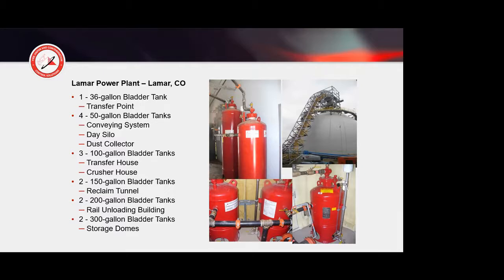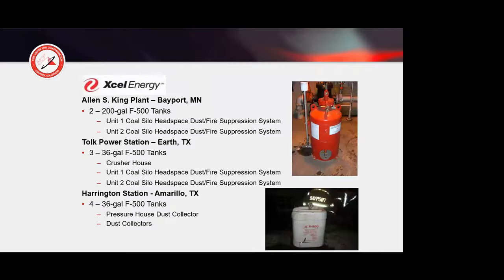Again, there's nothing in the code calling for this, and why they're being installed is because the plain water systems won't work and are actually a detractor and can cause an explosion. So they're putting this agent in to stop that. So usually our recommendation would be 15 minutes with 15 minutes of reserve. So here's a system up in Minnesota. This is used for a coal silo headspace for a fire washdown dust suppression system. These were used in the crusher house, here used in dust collectors.